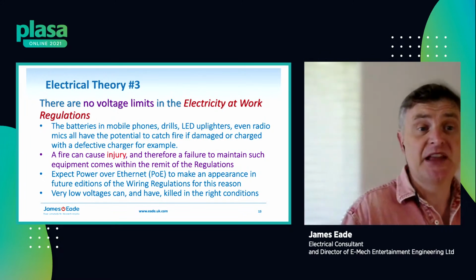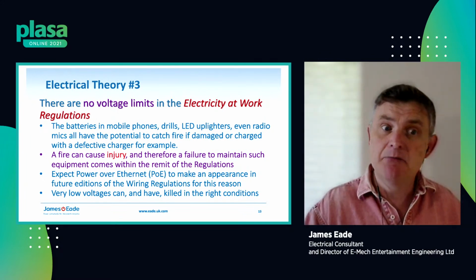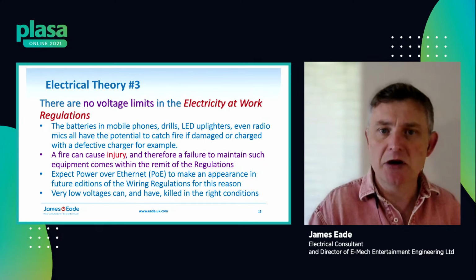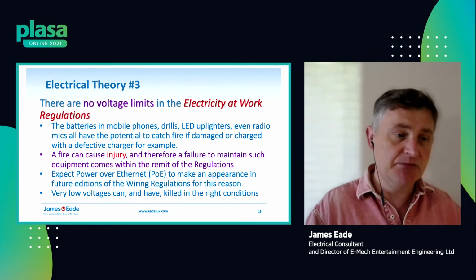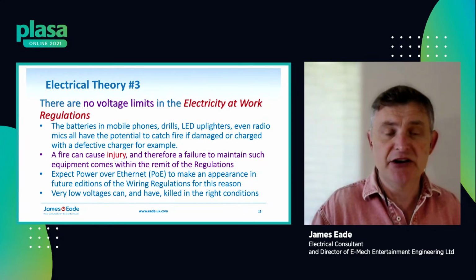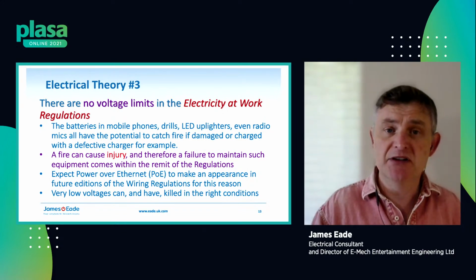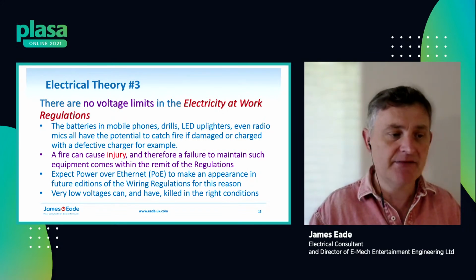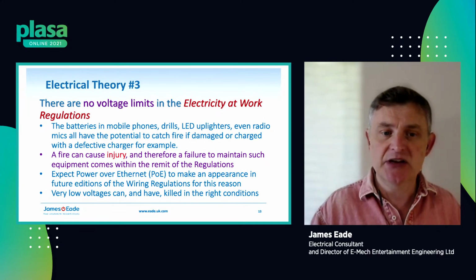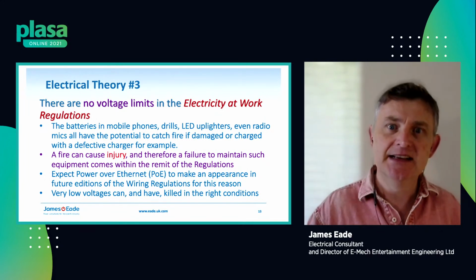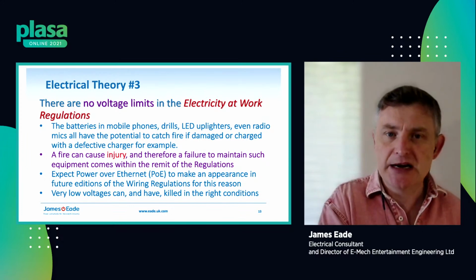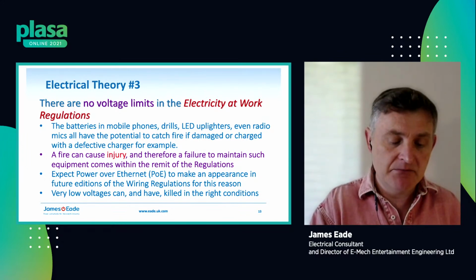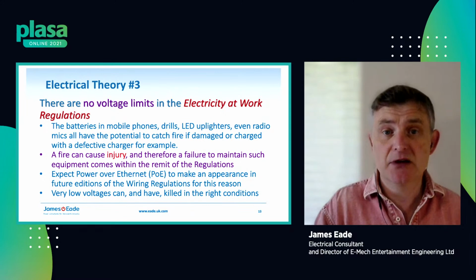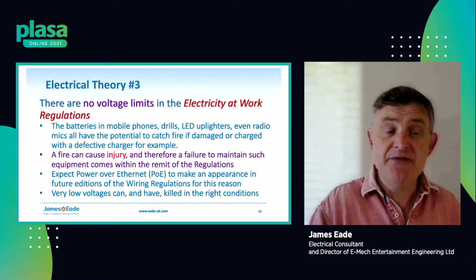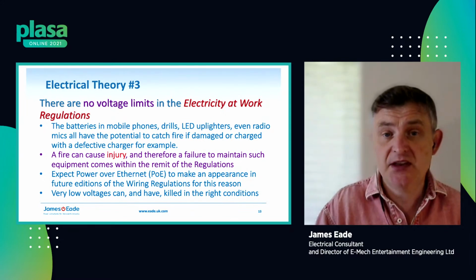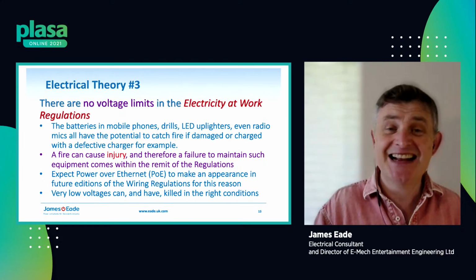For that reason, we can potentially expect to see Power over Ethernet systems coming into the wiring regulations in the future - something that's being worked on internationally in Europe at the moment. So it will eventually be embodied in BS 7671, the wiring regulations in the UK. And it's for that very reason that although the shock risk is very low, the fire risk is still very much present.